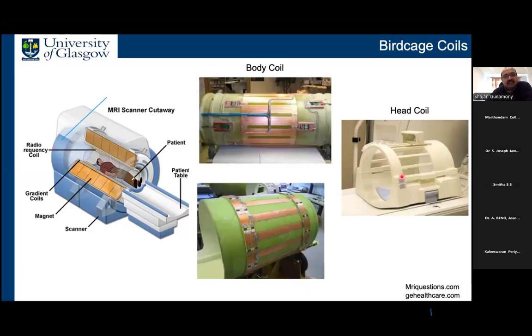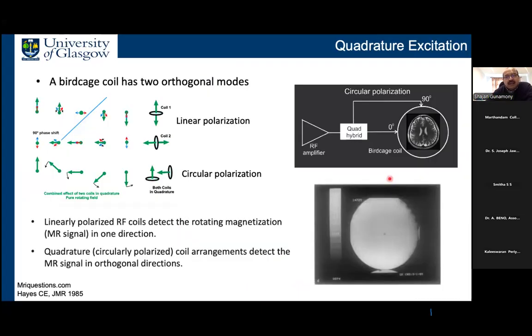And the head coil is much smaller. It's for imaging the brain. And a birdcage coil has 2 orthogonal modes. Suppose you have a coil which is horizontal like this, it produces a field vertical to the plane of the coil. This also means that we pick up the MR signal from the vertical direction. So if you have a coil oriented vertically, then it produces a field in the horizontal direction. And it also means that we pick up the MR signal from the horizontal direction. So this is called linear polarization.